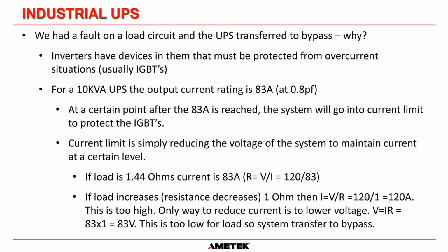And I think this is the last misconception. We had a fault on a load circuit and the UPS transferred to bypass. Why did it do that? So inverters have devices in them that must be protected from overcurrent. The way that the UPS switches the DC back into AC is using what's called an IGBT, which is an insulated gate bipolar transistor. And those transistors are very, very sensitive to high current situations. They will basically blow up if too much current flows through them.